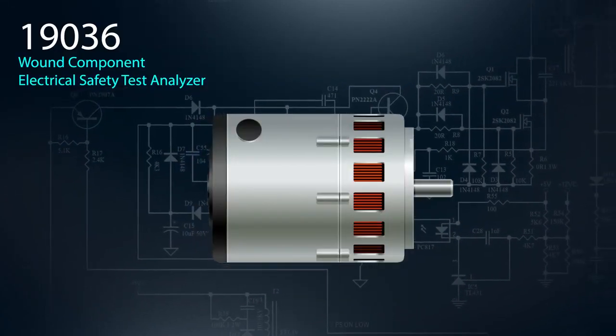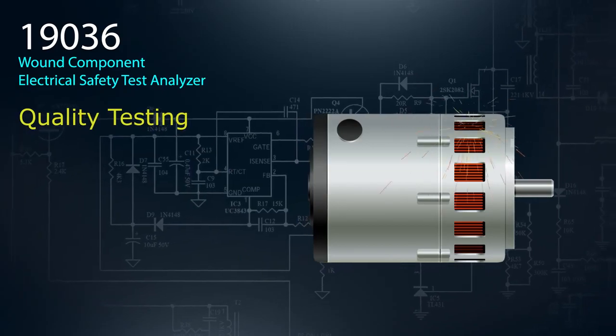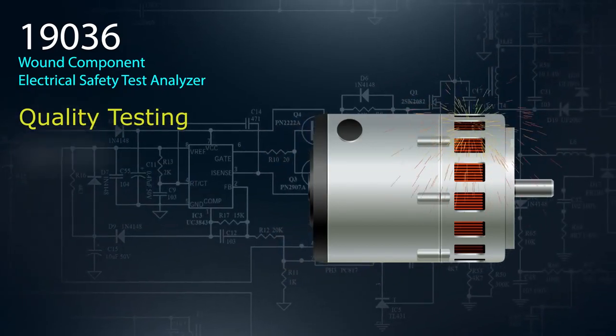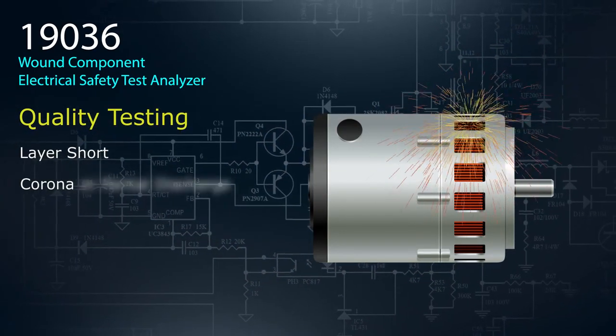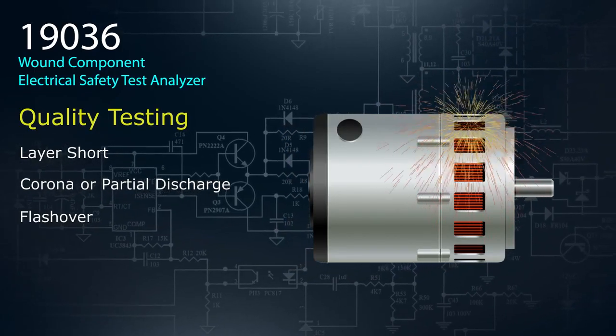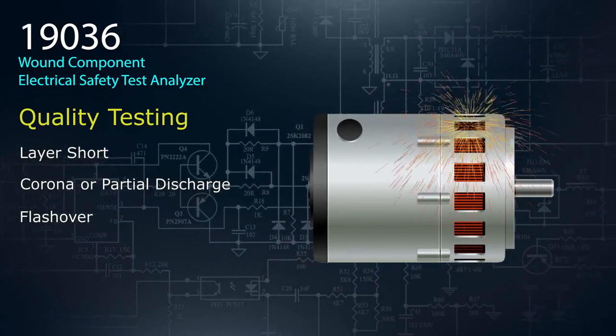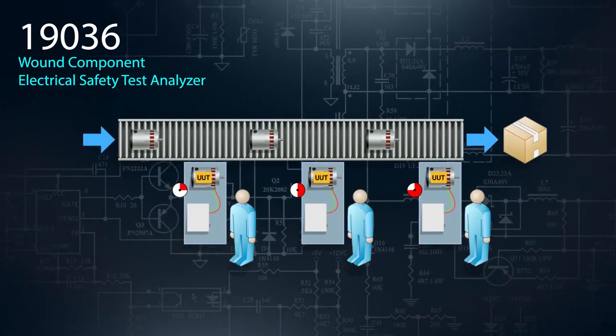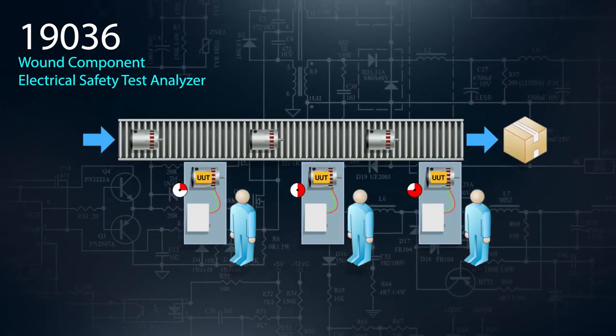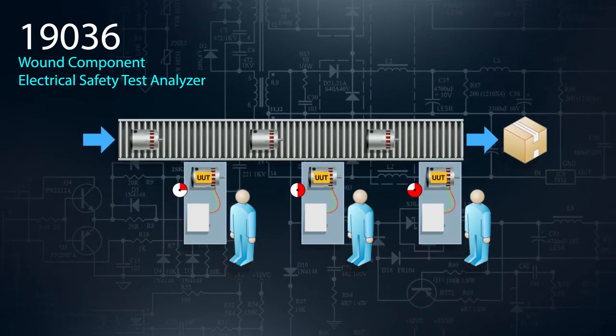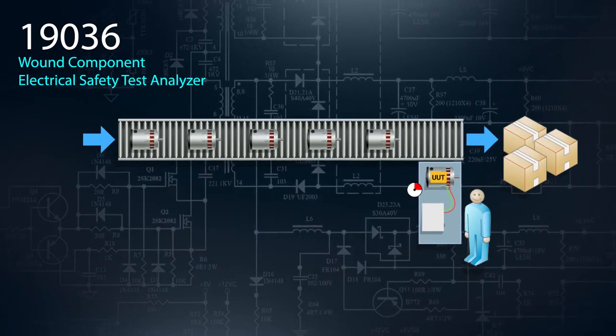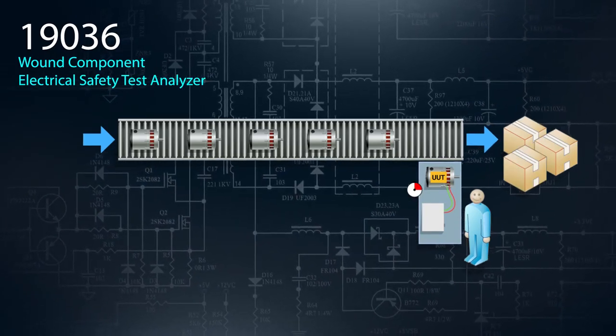Until now, quality testing for defects or even potential defects in wound components like a layer short, corona, partial discharge, or flashover has been difficult to perform during early phases of design and production. Several instruments and multiple test stations had to be active in order to comply with standards. Chroma has come up with a solution to free up resources and increase your throughput.